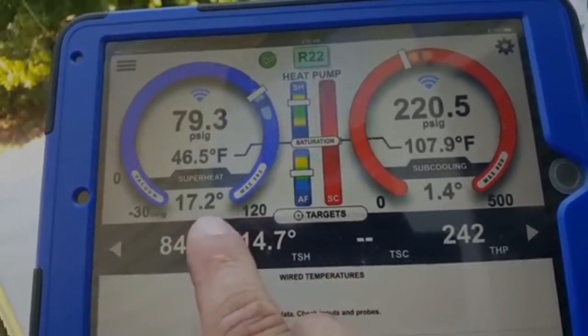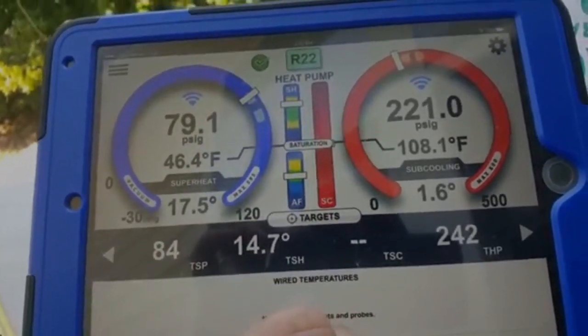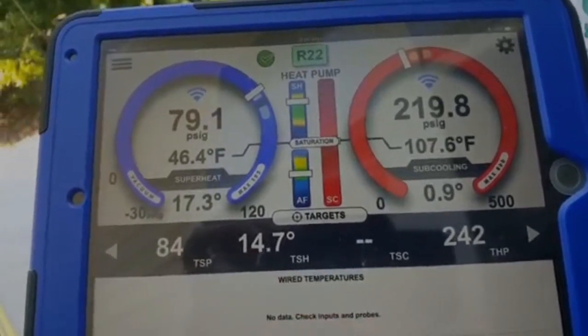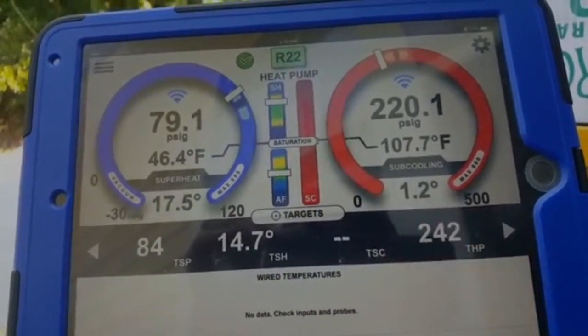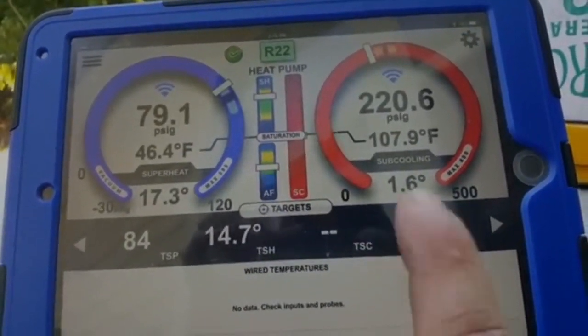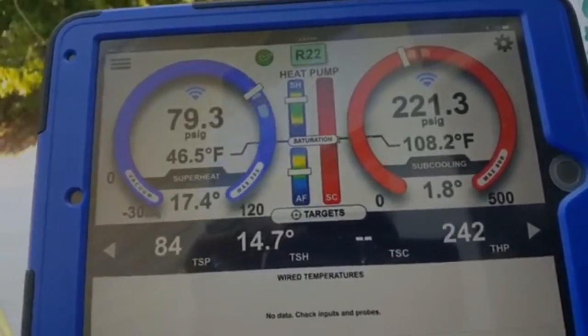This will keep bouncing around. Looks like it's going up a little bit now, but I like it right there. That's about as good as you can do on these sort of systems. You see how low the subcooling gets, but obviously it's a leaker too, so you figure out where it's leaking from. I am getting the leak detector ready. It's warming up. I'm gonna open up this door, see if we have a leaky evaporator. We're gonna be sneakers.